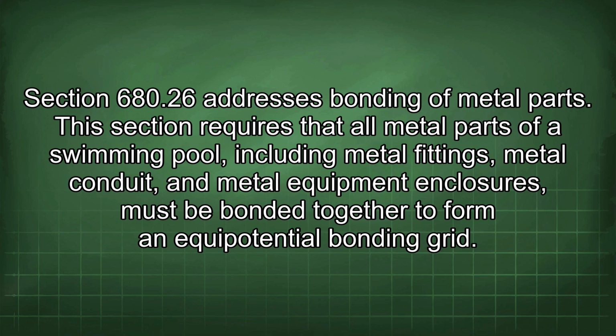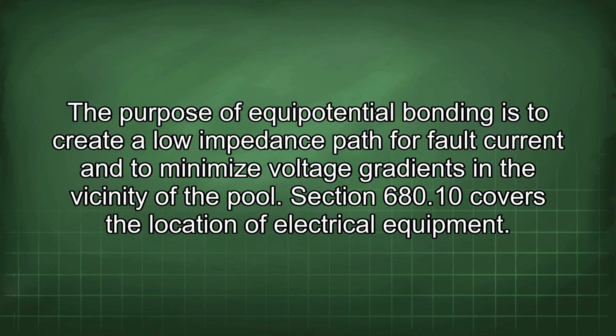Section 680.26 addresses bonding of metal parts. This section requires that all metal parts of a swimming pool, including metal fittings, metal conduit, and metal equipment enclosures, must be bonded together to form an equipotential bonding grid. The purpose of equipotential bonding is to create a low impedance path for fault current and to minimize voltage gradients in the vicinity of the pool.